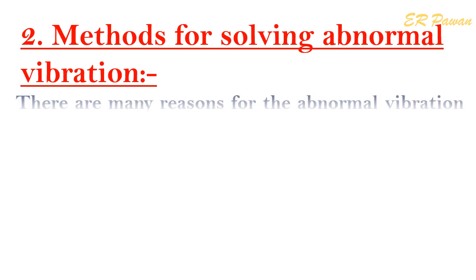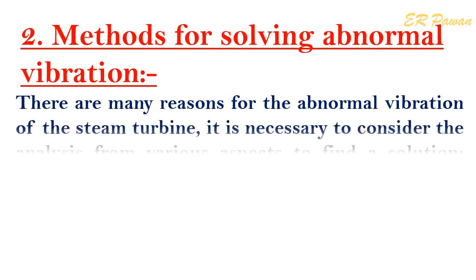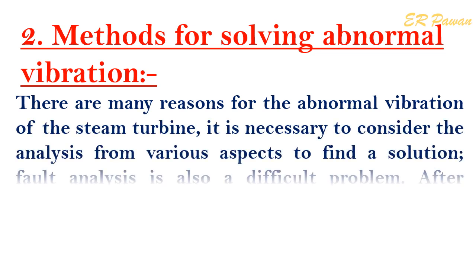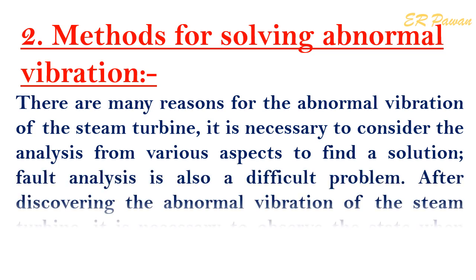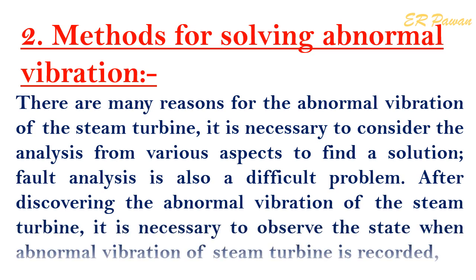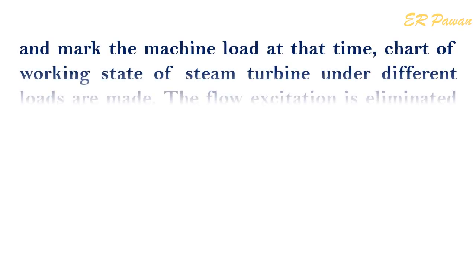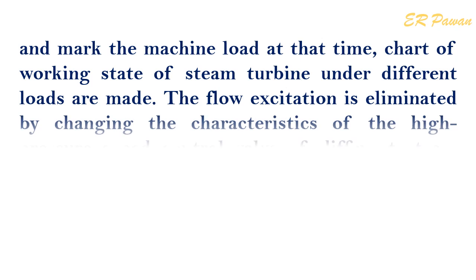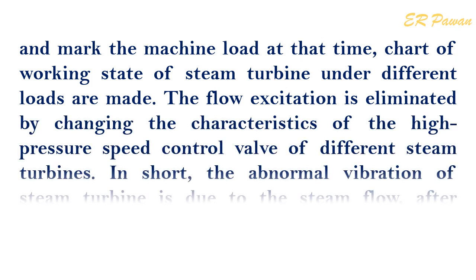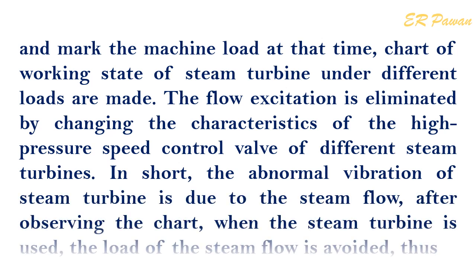Methods for solving abnormal vibration: There are many reasons for abnormal vibration of the steam turbine, and it is necessary to consider analysis from various aspects to find a solution. After discovering abnormal vibration, it is necessary to observe and record the state when it occurs, mark the machine load at that time, and make charts of the working state under different loads. The flow excitation is eliminated by changing the characteristics of the high-pressure speed control valve. When the steam turbine is used, the load of the steam flow is avoided, thus eliminating the flow excitation.